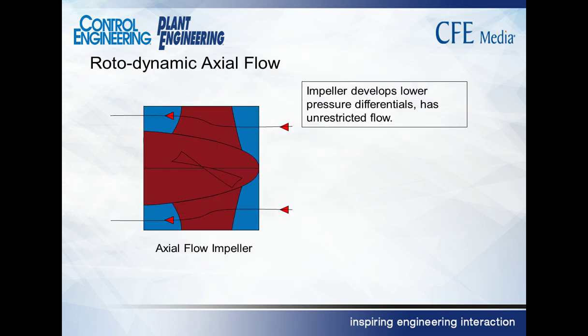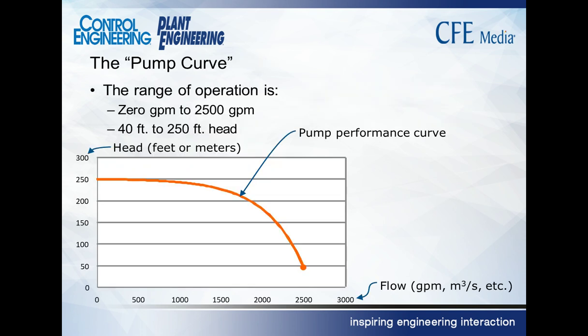Axial flow pumps are also rotodynamic pumps, and they have a pump curve. There's no opportunity here really for trimming the outside diameter of an axial flow pump, but reducing the speed will change the head and flow characteristics of the pump and can be used to adjust the size of the pump, if you will, to a particular application.